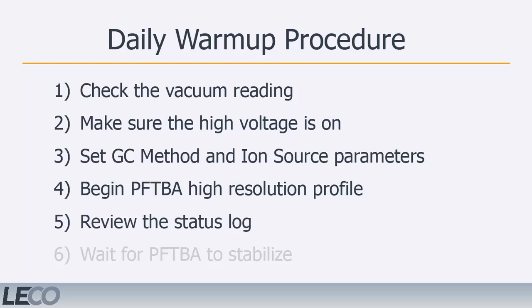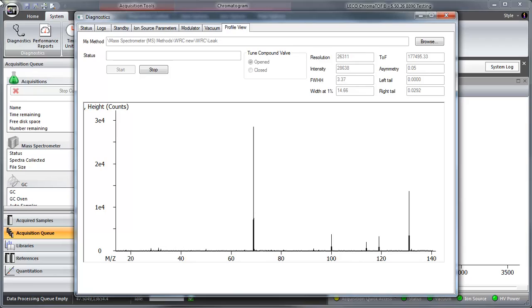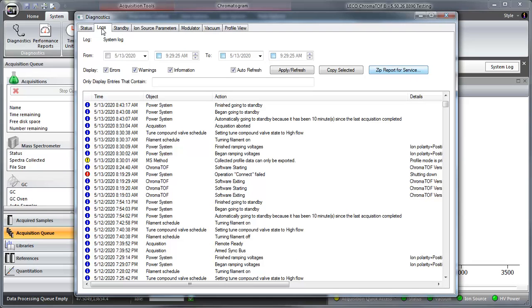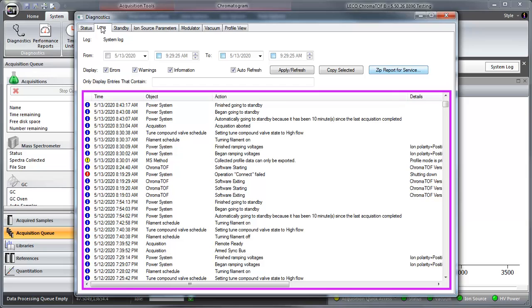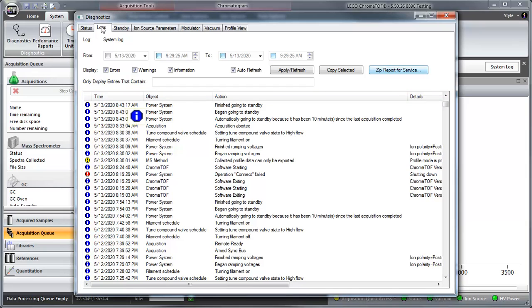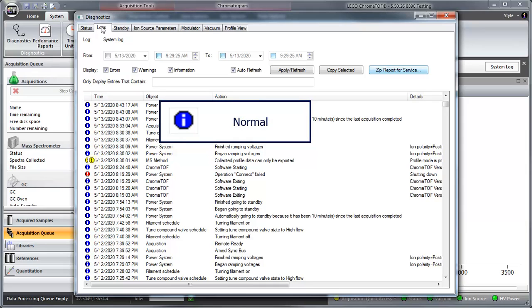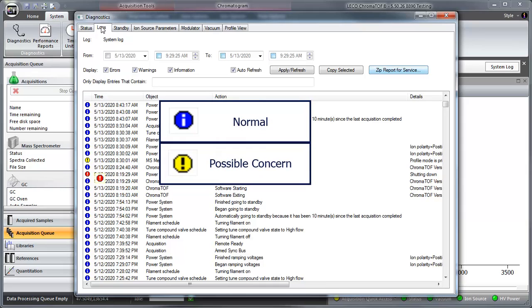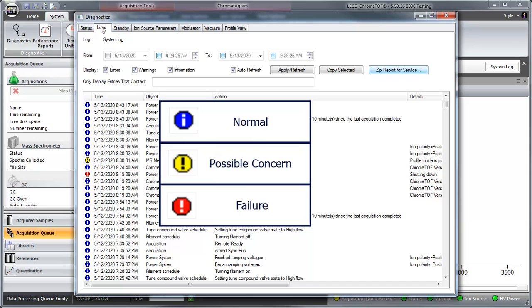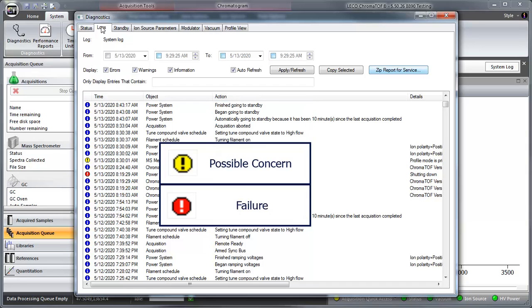Step 5. Review the status log. While PFTBA profiling continues, click on the Status tab within the Diagnostics window to access the system log. The system log records each step taken by the ChromaTOF software. Each of these steps is given a status icon of either blue, which means normal, yellow, a possible concern, or red, a failure. Red and yellow warnings also display in a message bar beneath the menu ribbon.